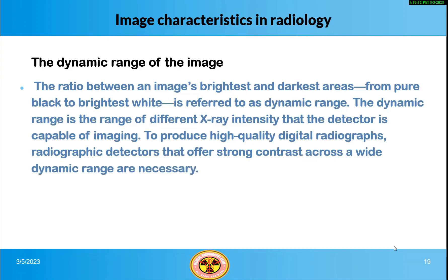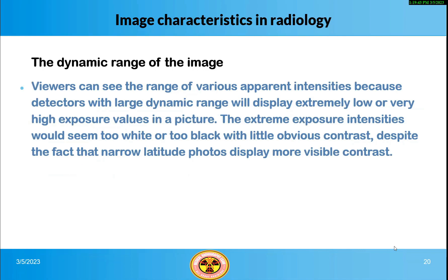The dynamic range of the image is the ratio between an image's brightest and darkest areas, from pure black to brightest white. The dynamic range is the range of different x-ray intensities that the detector is capable of imaging. To produce high-quality digital radiographs, radiographic detectors that offer strong contrast across a wide dynamic range are necessary. Detectors with large dynamic range will display extremely low or very high exposure values in a picture, while extreme exposure intensities would appear too white or too black with little obvious contrast in narrow latitude images.